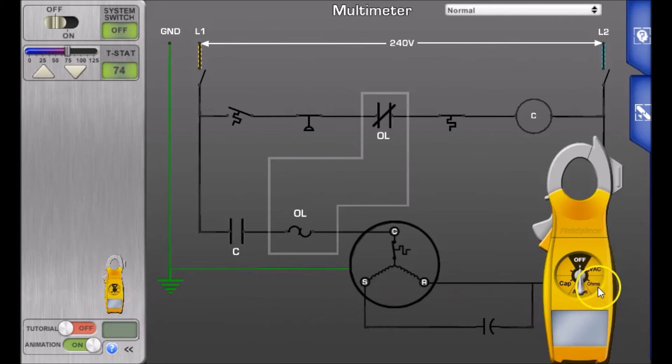So you grab your meter and you're going to switch it to ohms and we are going to measure between the common and the run winding and that gives us a resistance measurement of two ohms. Then you're going to measure between the common and the start winding. That gives you a resistance measurement of 10 ohms.